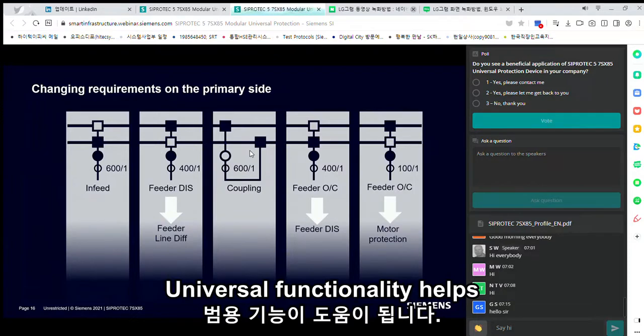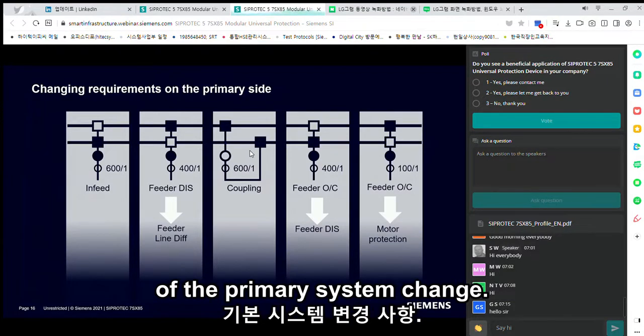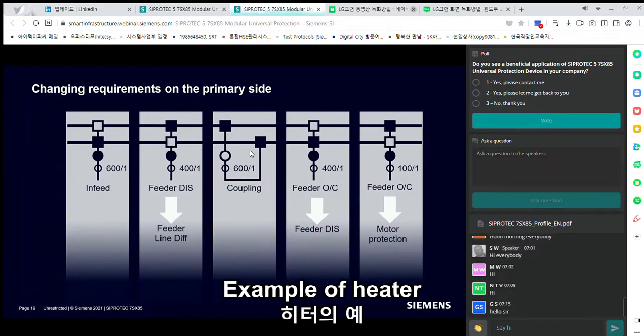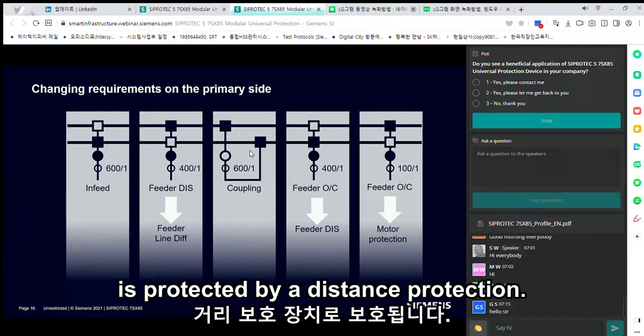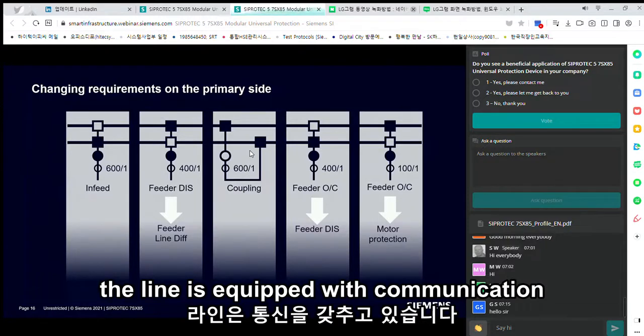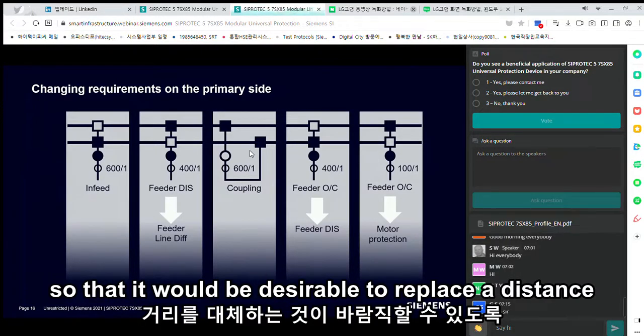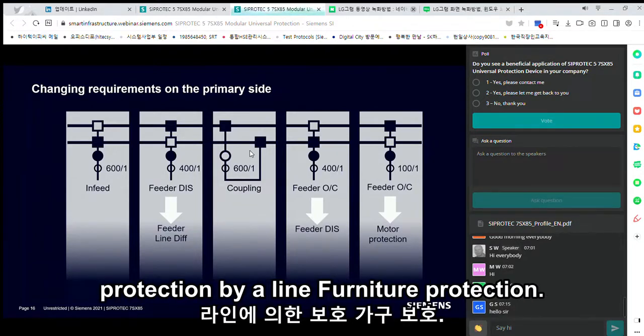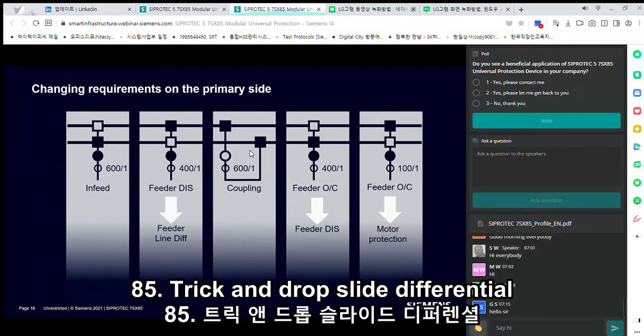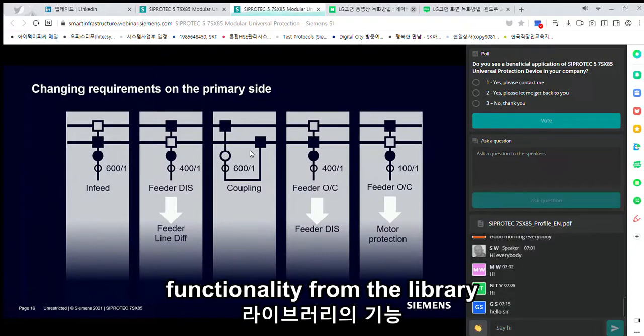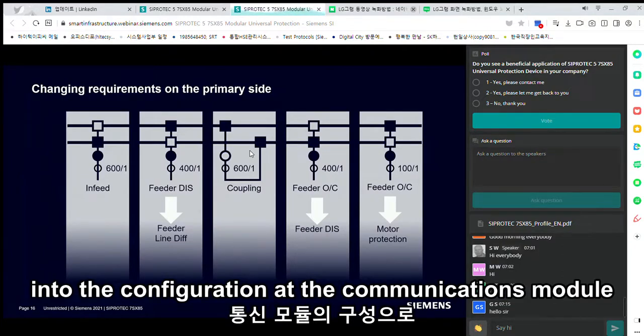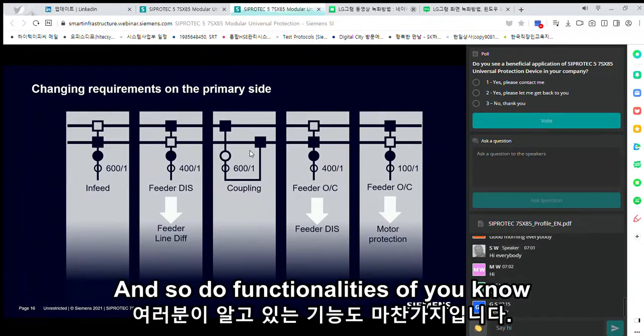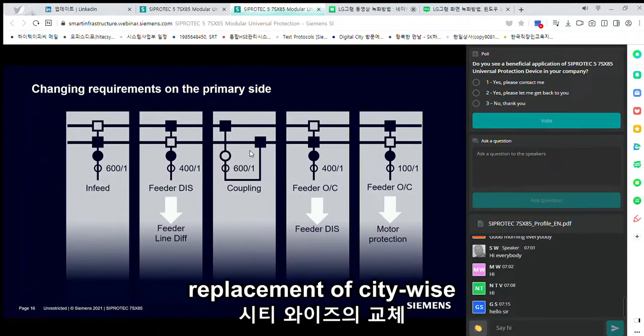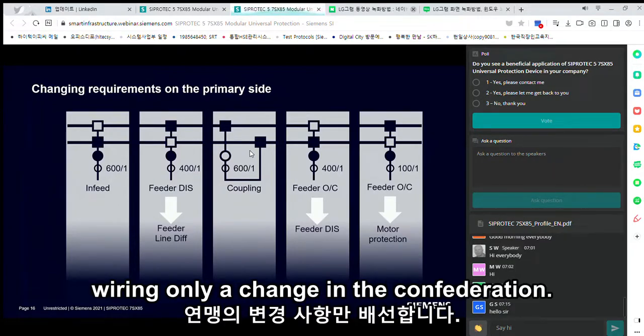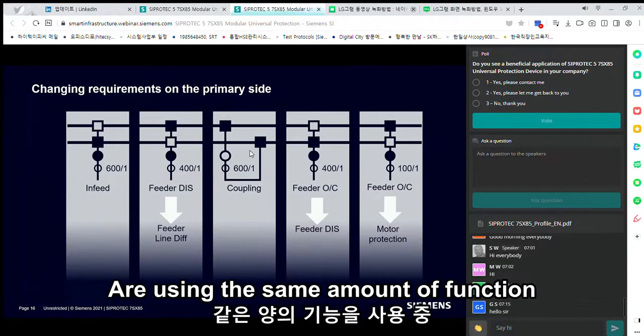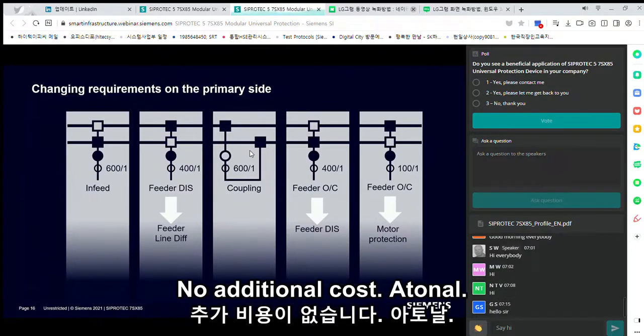The universal functionality helps even when the requirements of the primary system change. For example, a feeder is protected by a distance protection, and after some time of operation, the line is equipped with communication, so that it would be desirable to replace the distance protection by a line differential protection. No problem with the 7SX85. Drag and drop the line differential functionality from the library into the configuration, add the communications module to the hardware, and the new functionality is available. No replacement of the device, no new wiring, only a change in the configuration. Both functions are using the same amount of function points, therefore there will be no additional costs.